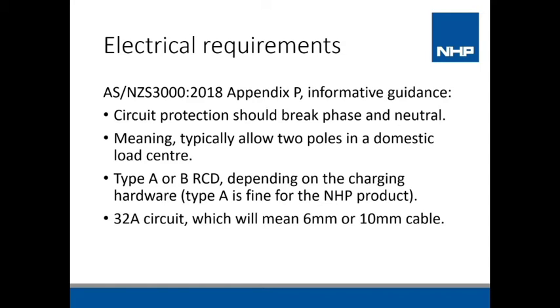Last note on this slide, 32 amp single phase circuit for typical domestic install. So I mentioned 7 kilowatt AC, 32 amp, that'll typically mean 6 or 10 mil cable. Obviously it depends on installation. All the standard voltage drop calculations and whatnot apply.